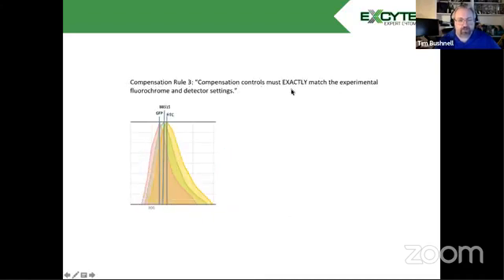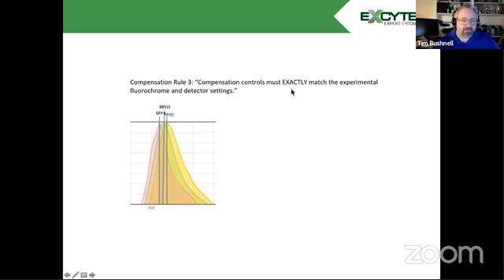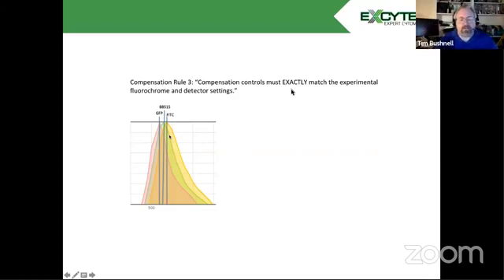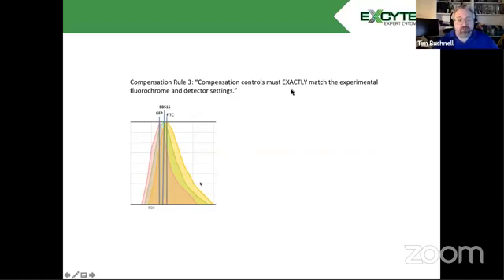And of course, the third important rule is that compensation controls must exactly match the experimental fluorochrome and the detector. And we're just showing here GFP, Brilliant Blue 515, and FITC. And you can see each of these, which will all be measured in the same detector, the FITC detector typically, say a 530-30 bandpass filter off the 488 laser. But they have very different spectral curves. The use of spectral viewers is really good for this to figure that out. So we're going to move from our slideshow here.